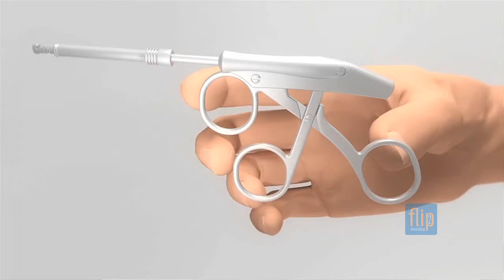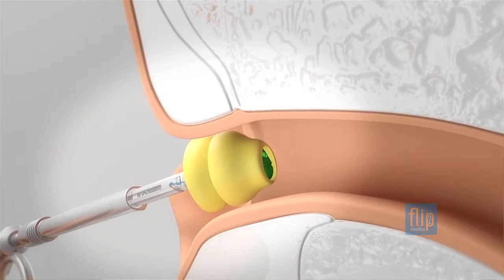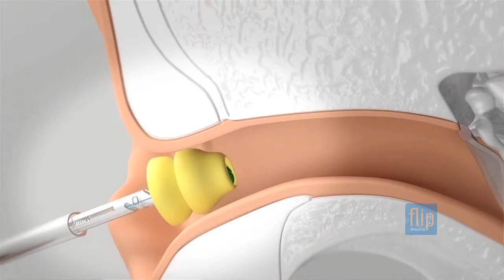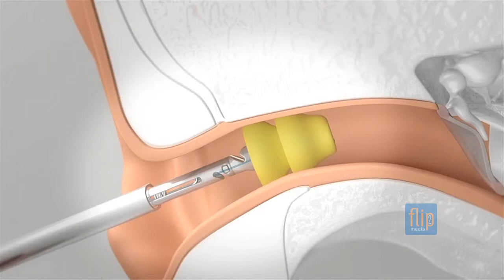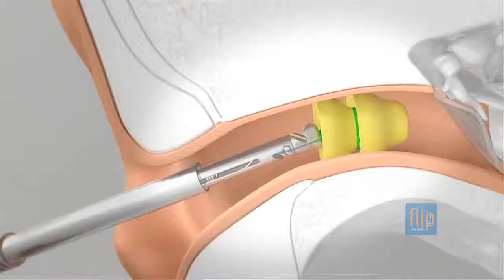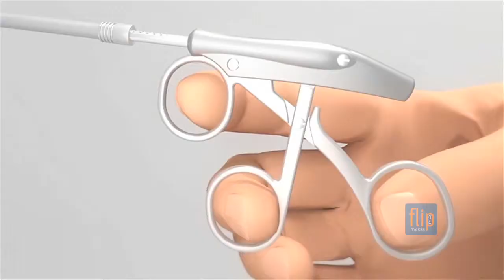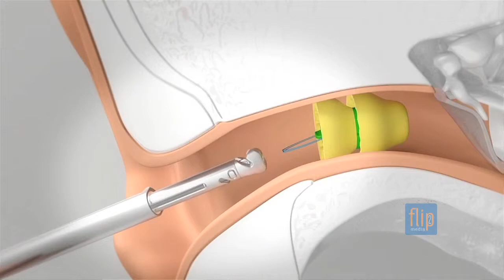The Lyric 2 insertion tool is quite a bit different than the insertion tool used for Lyric 1. The reason we had to change to a new insertion tool was Lyric 1 has a joint in the device, and so as the device is pushed into the ear canal with the insertion tool, it can migrate around bends. Whereas Lyric 2 is a shorter device with no joint. So what we did is we took the joint out of the Lyric 1 device and put it into the insertion tool for Lyric 2.